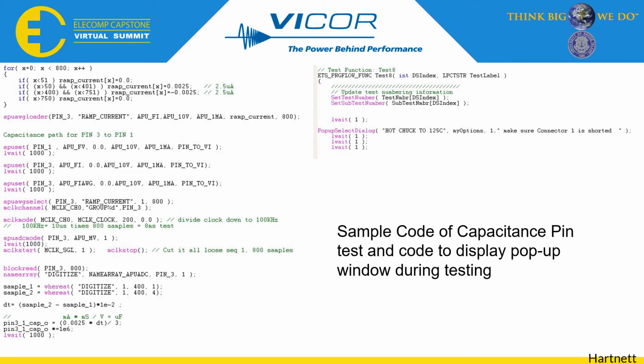Once the resistance tests and open capacitance tests were done, a pop-up display prompt pauses the test and informs the user to insert the shorting block into the corresponding connector that has the pins being tested on it. This shorting block shorts all the pins and allows for the capacitance measurements. Once all the connectors have been shorted, the test is complete.